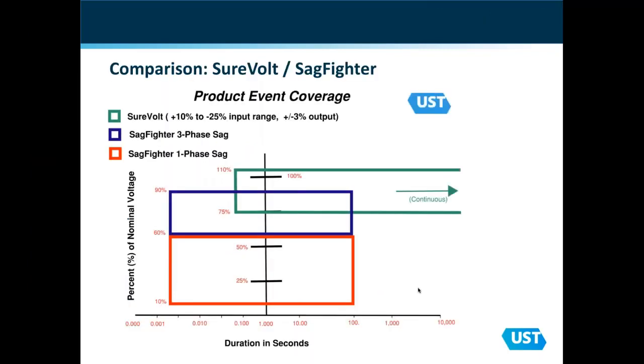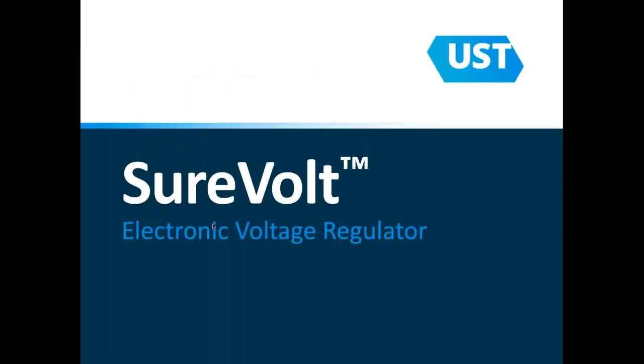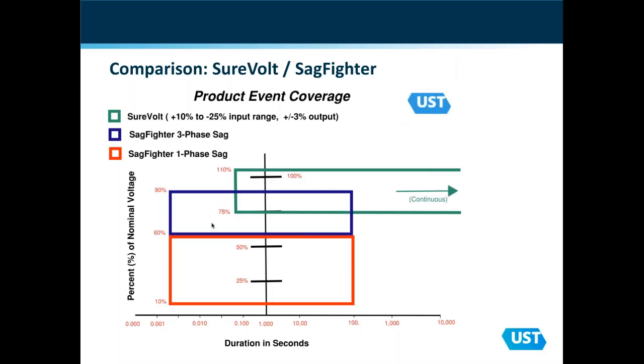To separate the 2 products, we have a graph that indicates, sorry about that. Let me back up. On the vertical axis you have voltage, and on the horizontal axis you have time. So the green box indicates a good application for the Surevolt product, which is our voltage regulator, and you can see it will correct for voltage between 75 and 110% of nominal, and it'll do this correction continuously.